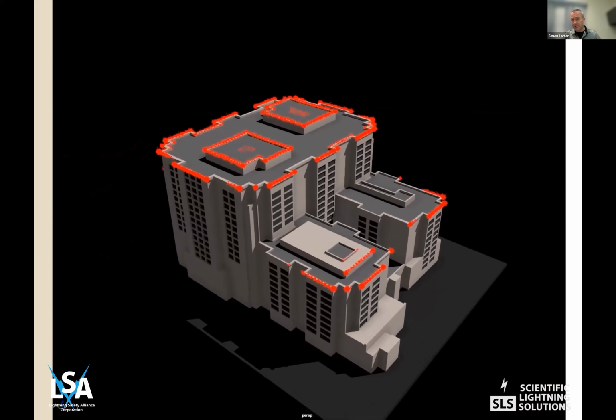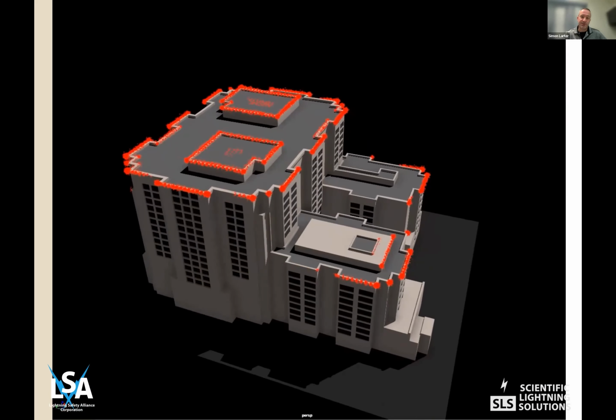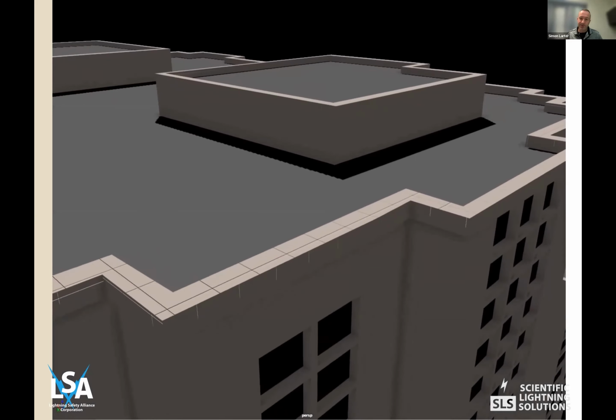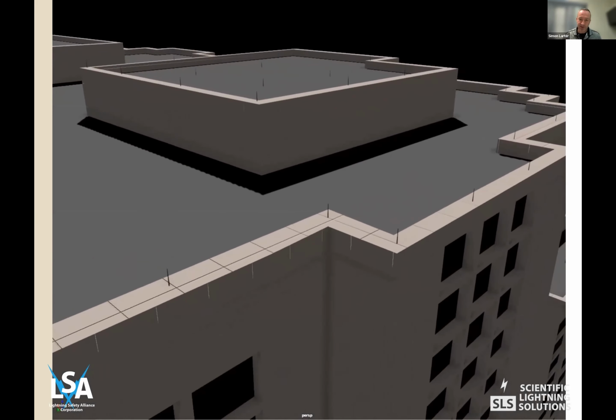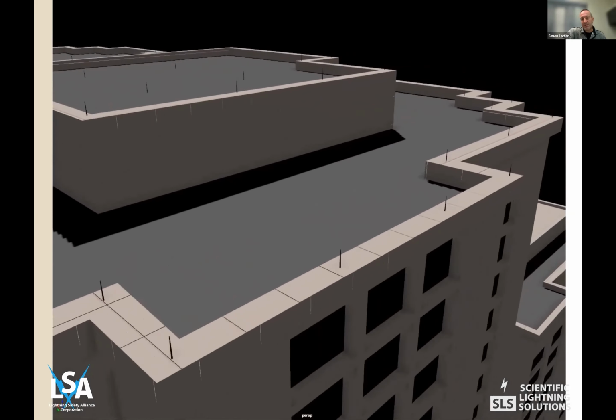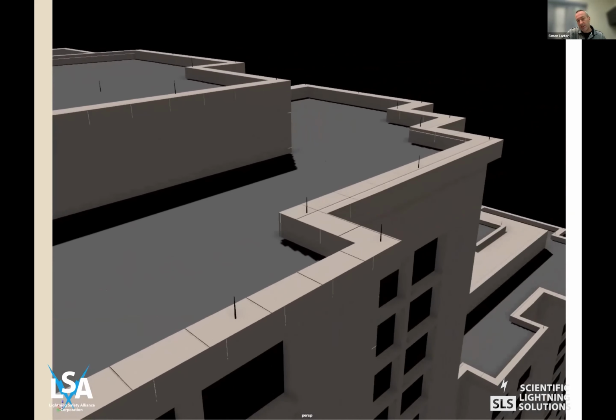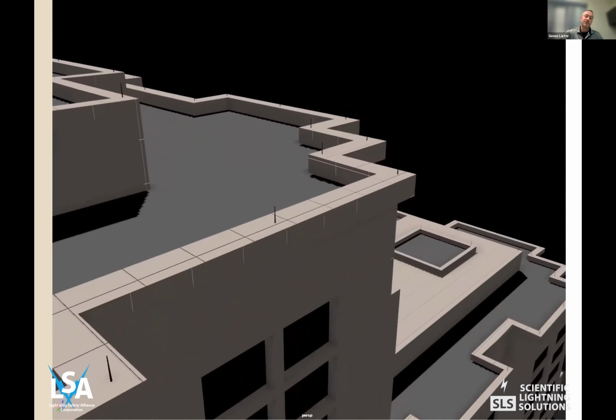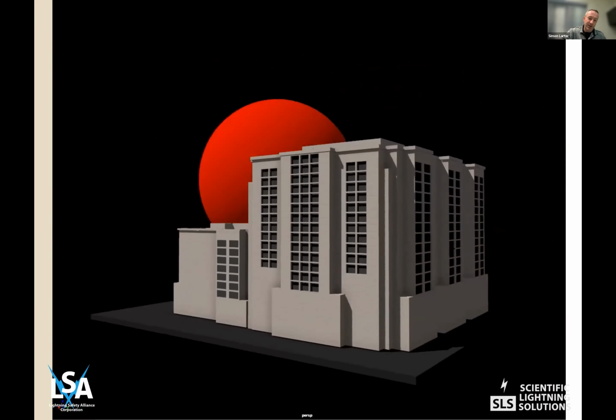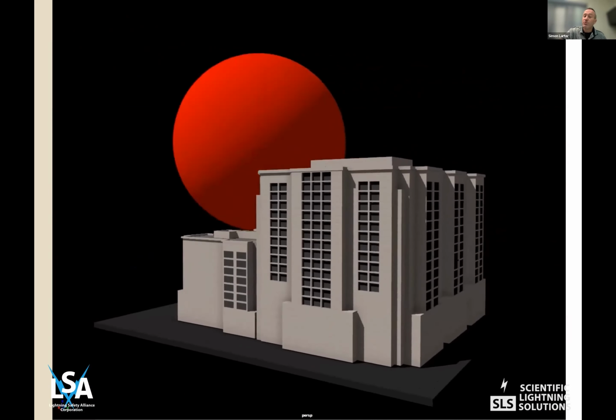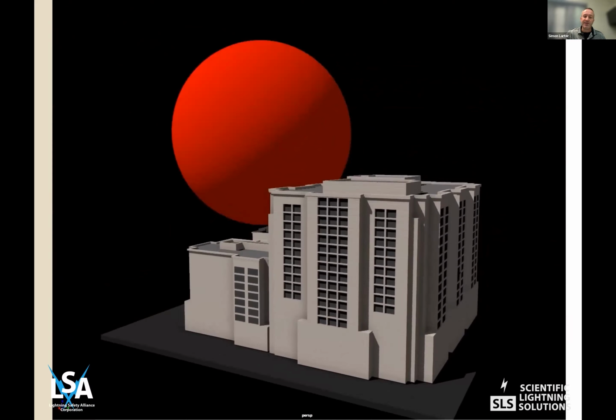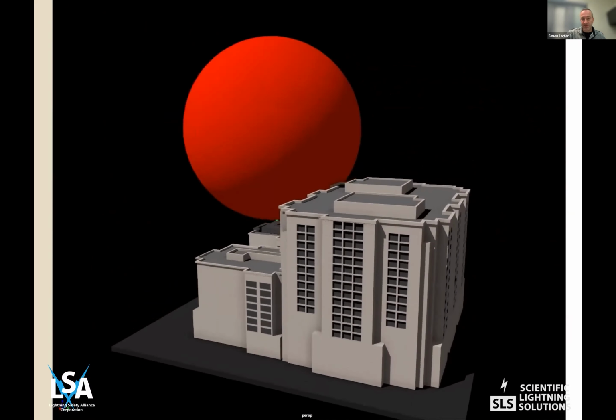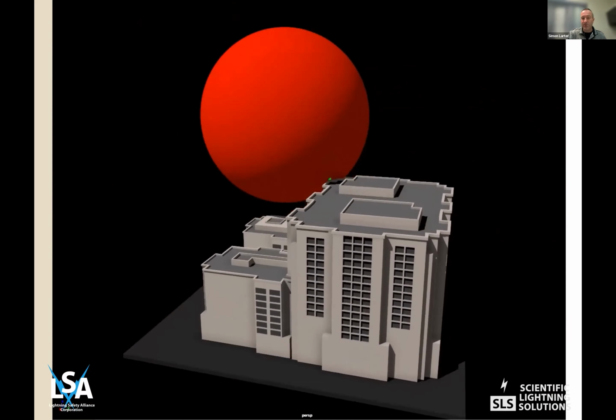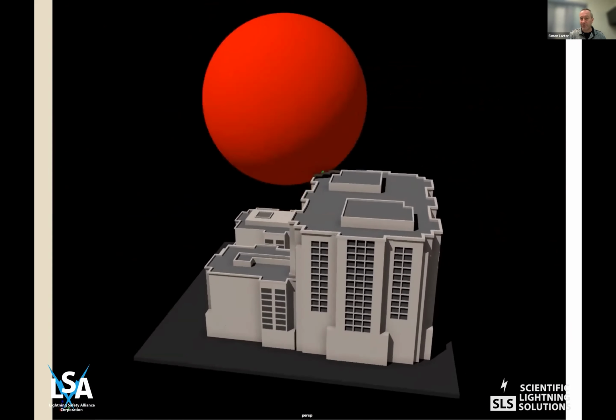You can see those are all the places that the rolling sphere touched, so we're going to want to protect those places. So why don't we put lightning protection on? Let's get those lightning rods in place, the conductors, the down conductors, the bonding connections, the grounding, and the surge protection for the full 5 elements of a lightning protection system. Now when you roll the sphere up and over, it's hitting the lightning protection system and not the building itself.